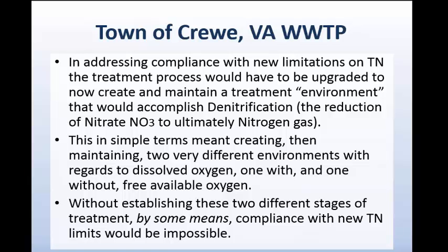In simple terms, this meant creating and then maintaining two very different environments with regards to dissolved oxygen in our plant. We had to maintain one with, and we had to create and maintain one without free available oxygen. The facility always had maintained excellent efficiency in the nitrification process.